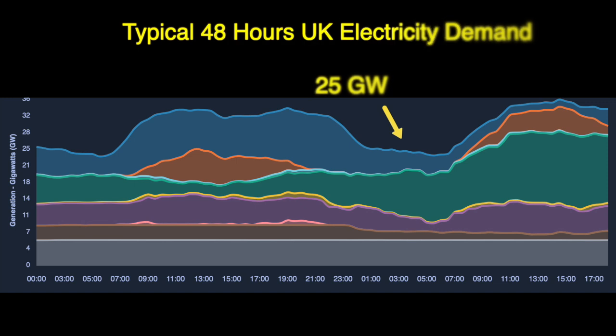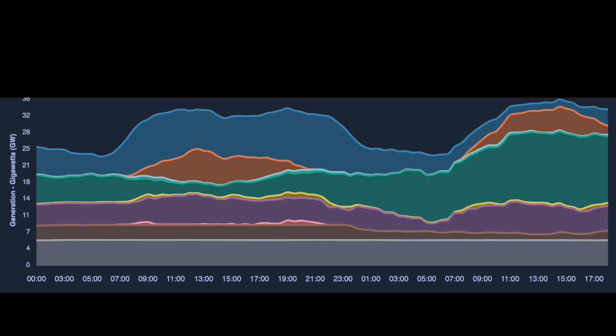That is very different to trying to balance intermittent energy such as wind. With wind, in the case of Dinorwig, 9.1 gigawatt hours are stored. But overnight we're using around 25 gigawatts in Britain, and in the day around 38. You've got 1.7 gigawatts maximum coming out, but even the full 9.1 gigawatt hours — it's gone in 20 minutes.